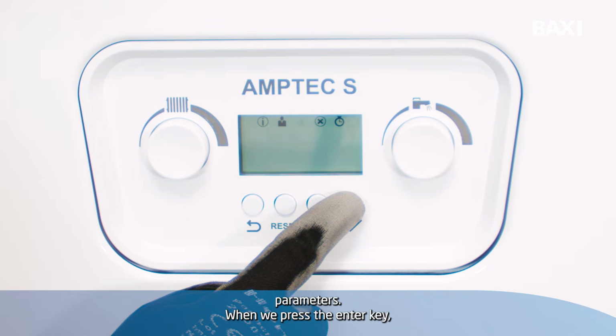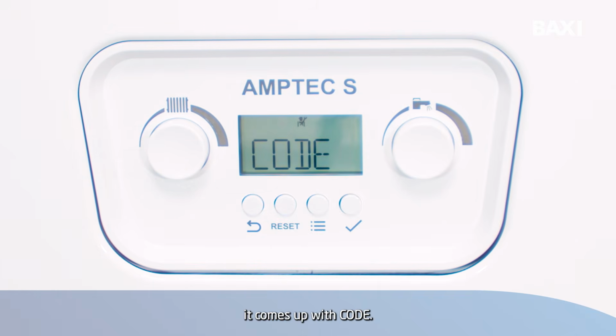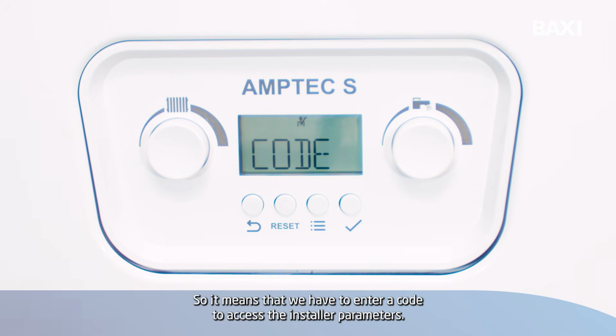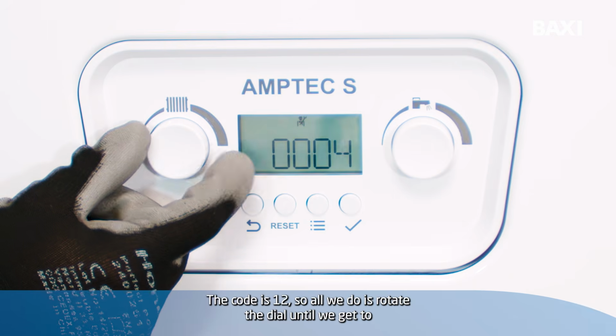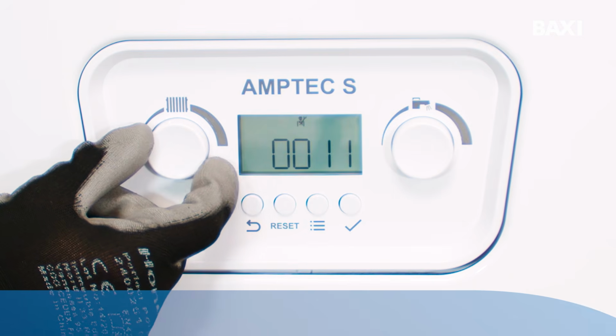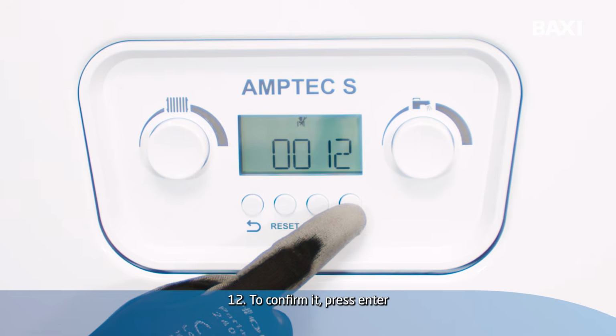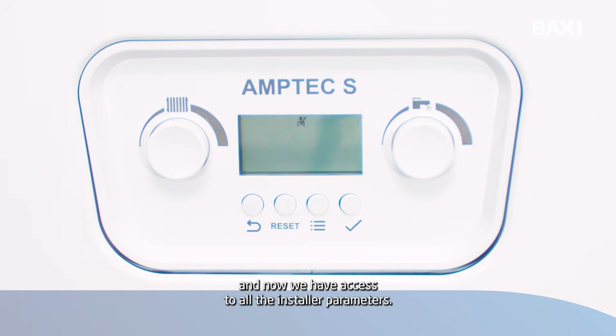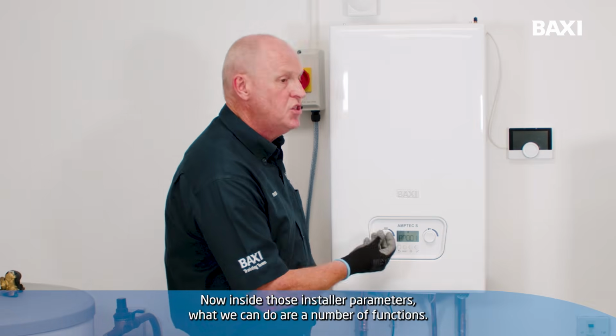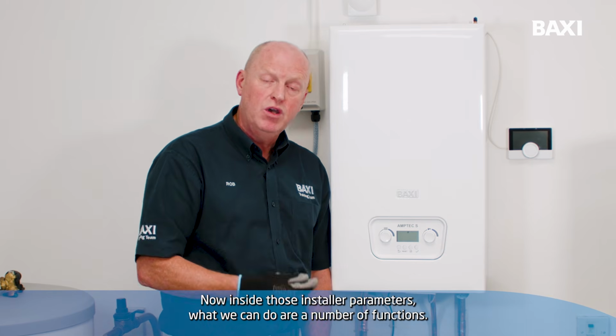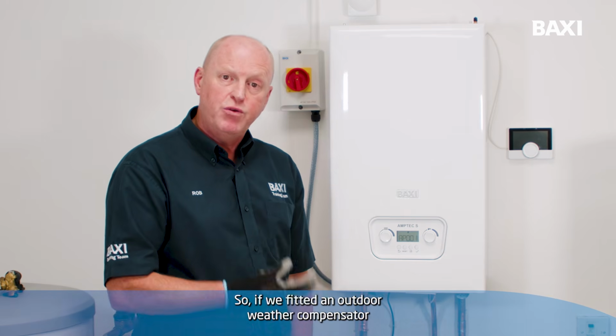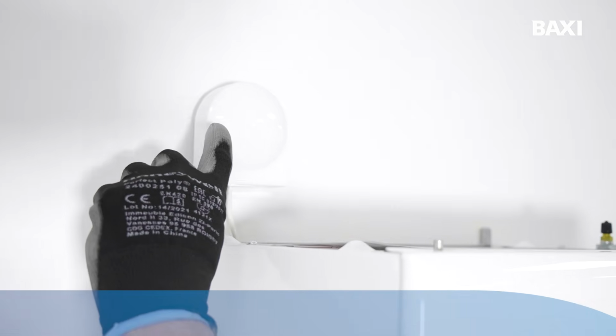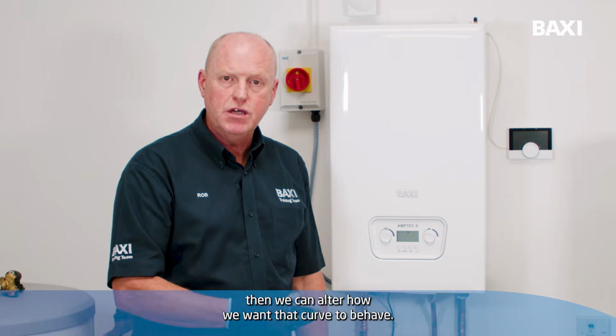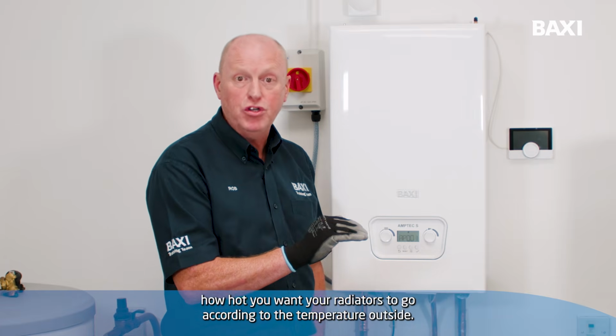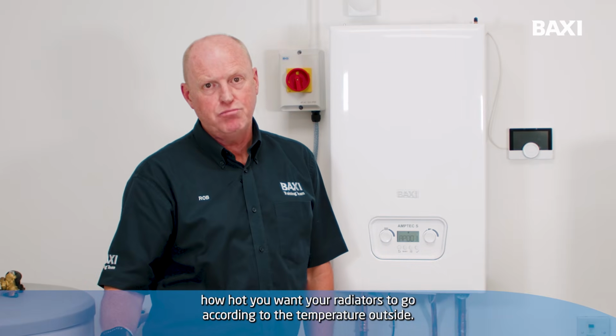When we press the enter key, it comes up with code. So it means that we have to enter a code to access the installer parameters. The code is 12, so all we do is rotate the dial until we get to 12. To confirm it, press enter, and now we have access to all the installer parameters. Now inside those installer parameters, what we can do are a number of functions. So if we fitted an outdoor weather compensator, then we can alter how we want that curve to behave. So basically how hot you want your radiators to go according to the temperature outside.